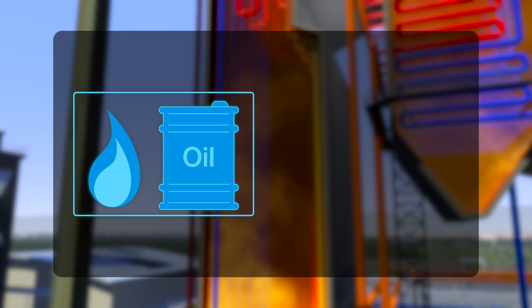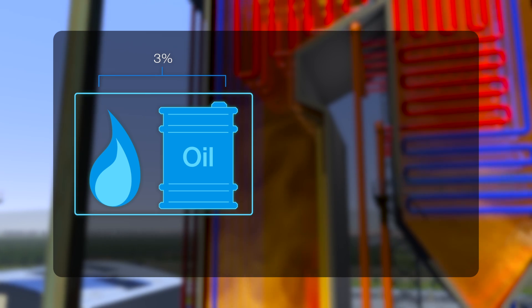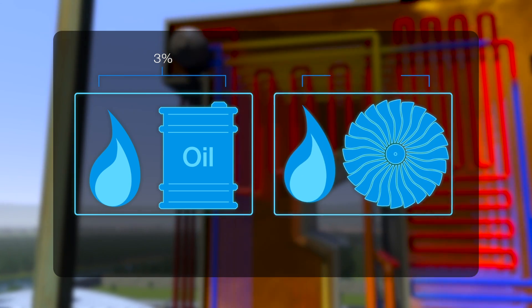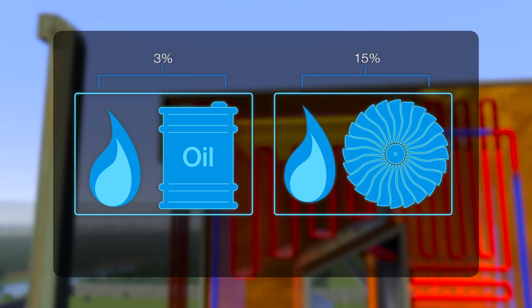Gas or liquid fuels, for example, will have an oxygen reference value of 3%, which is much lower than the 15% used in gas turbine processes.